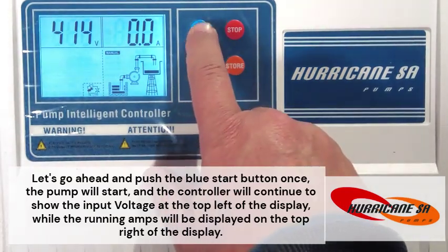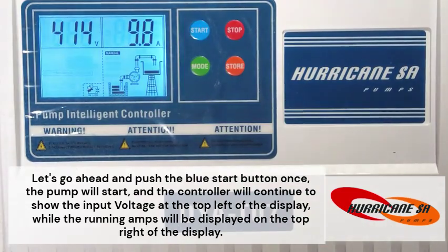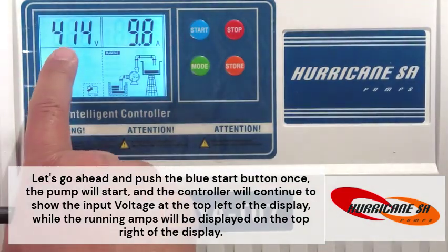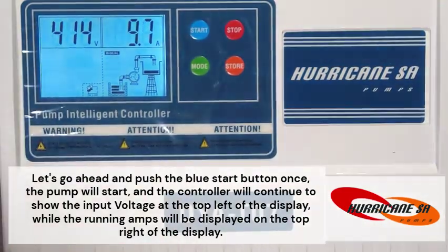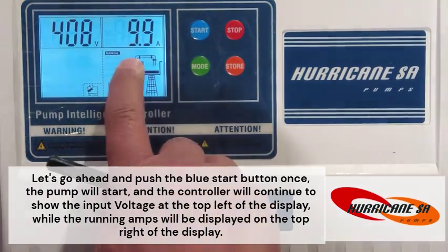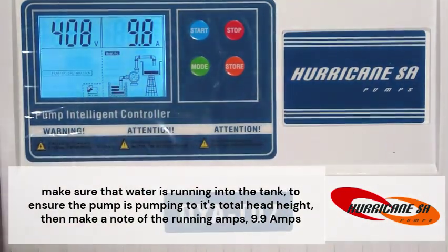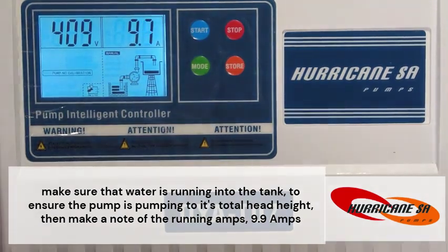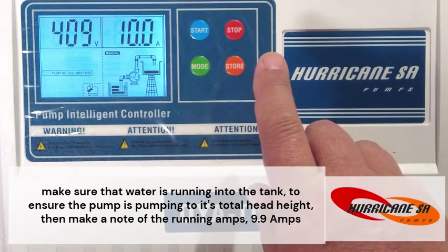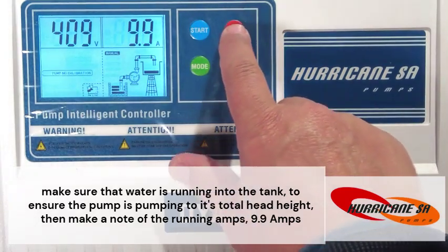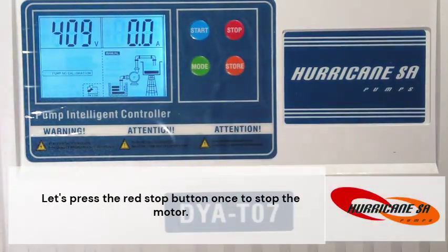Let's go ahead and push the blue start button once. The pump will start and the control will continue to show the input voltage at the top left of the display, while the running amps will be displayed on the top right of the display. Make sure that water is running into the tank to ensure the pump is pumping to its total head height, then make a note of the running amps, 9.9 amps. Let's press the red stop button once to stop the motor.